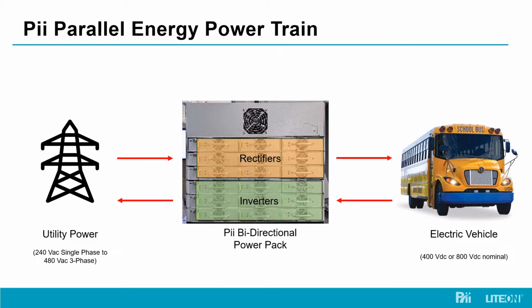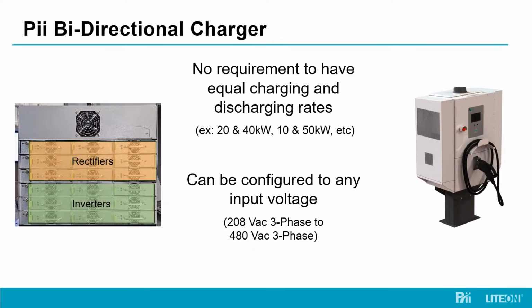And because the rectifiers themselves are very highly input agnostic, taking 208 up to 480 three-phase, the inverters do likewise. So it can power match for whatever overall power distribution topology is required of the application. That's not to say that you need equal charging and discharging. So with PII's bidirectional charging system, you're able to charge and discharge at different rates.